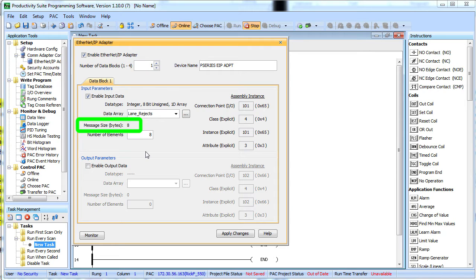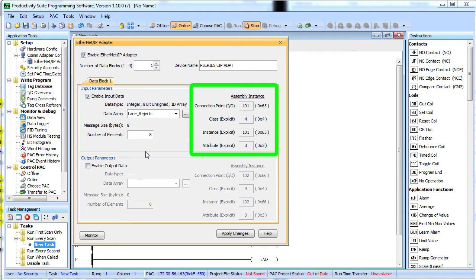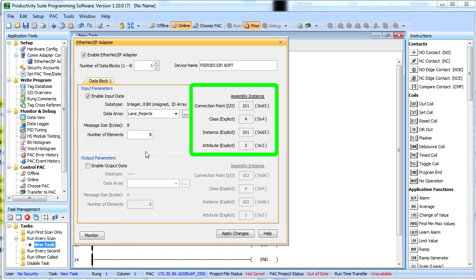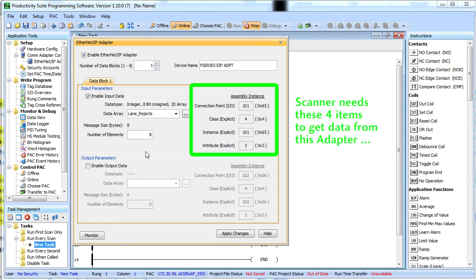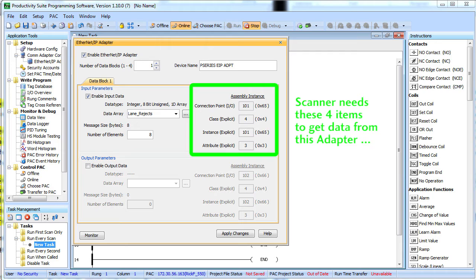Message size will be 8 bytes going back to the scanner. These guys over here are automatically generated, so you don't have to worry about filling them in. But, you do want to make note of them because it's these 4 items that you'll need to set up the scanner. The scanner video configures the scanner to talk to this adapter so you can see how this all fits together. For now, just know that this is key information so keep it handy.